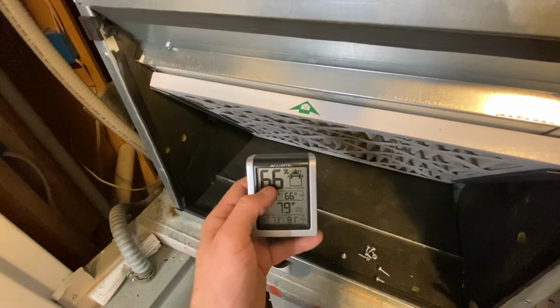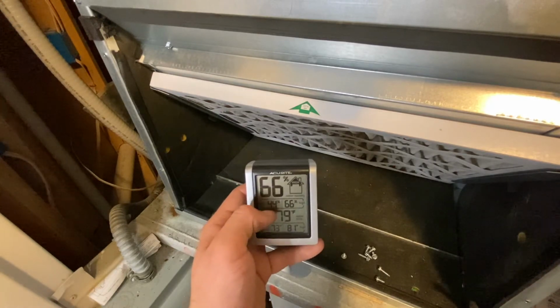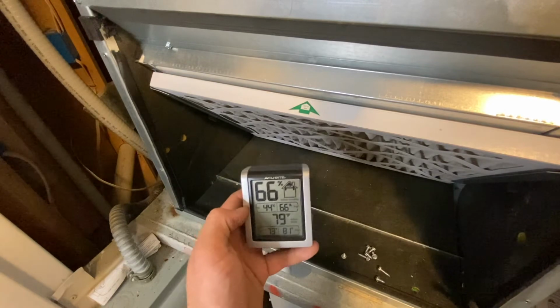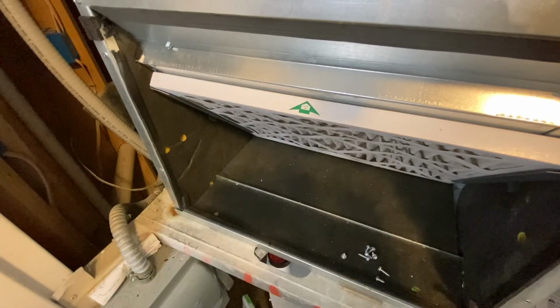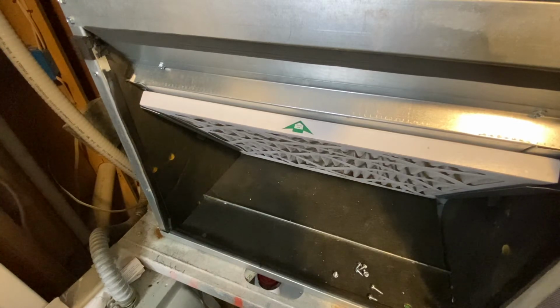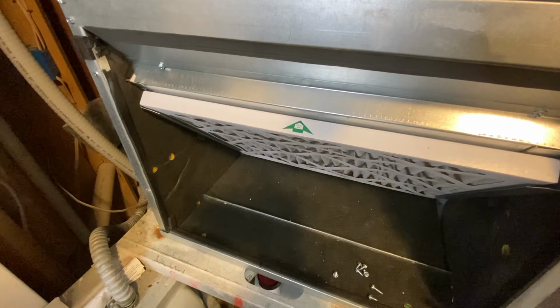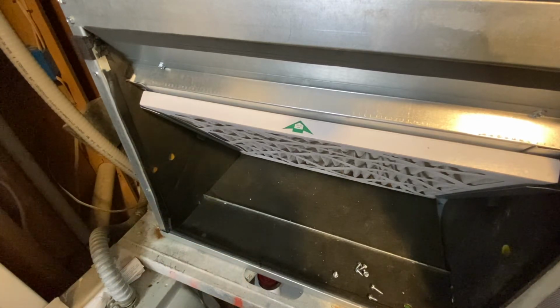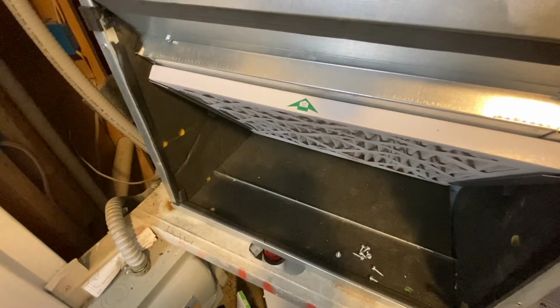I think it will, just because the air handler is going to do a better job of removing moisture from the air. So keep an eye on that. As you can hear, the fan speed has picked up a little bit. The temperature on my thermometer that I have in the supply air duct is reading 56 degrees, so the fan speed should level out around here. According to my thermometer in the supply air duct, the temperature is 57 degrees, so it should hold steady. The fan speed should start leveling out around here once it hits 55 degrees.